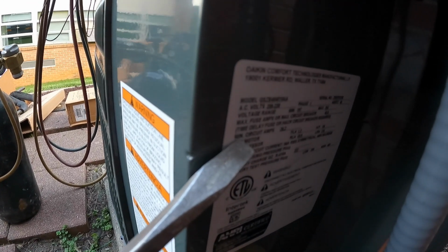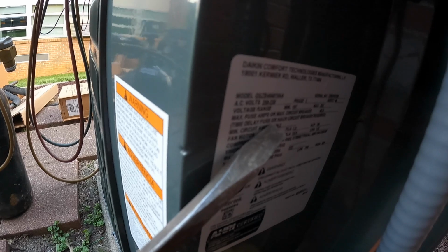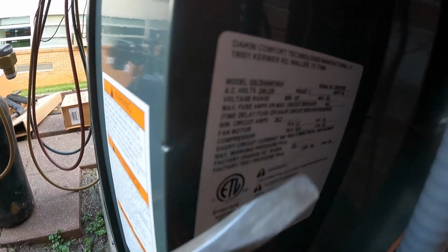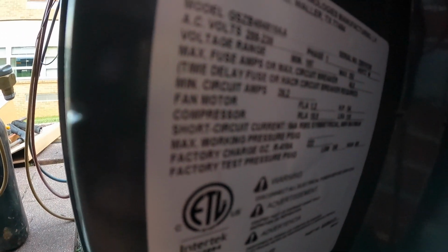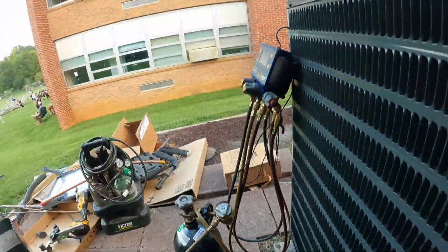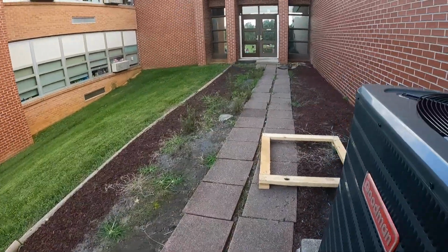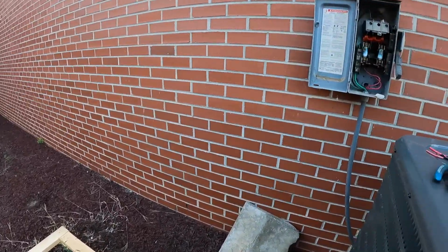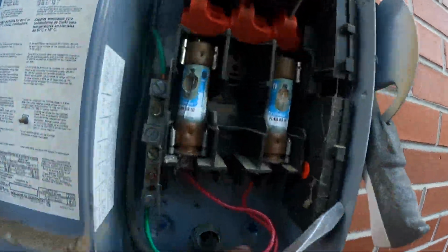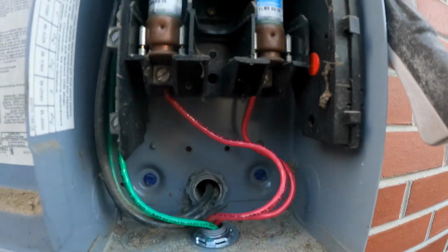Okay, if you look right here on the label, it says minimum circuit amps 26.2. And then the maximum fuse or circuit breaker is 45. So the 26.2 is how you size your wire. So I'll put number 10 wire, which will be good for 30.